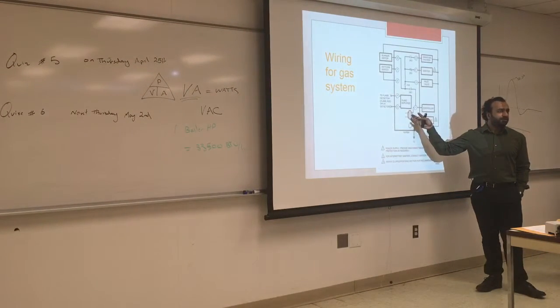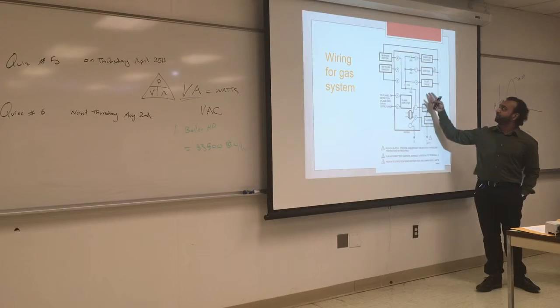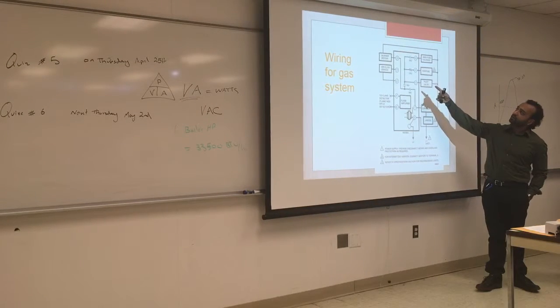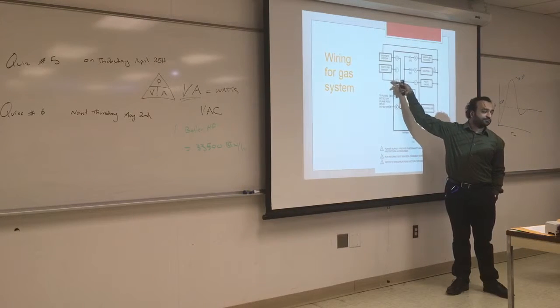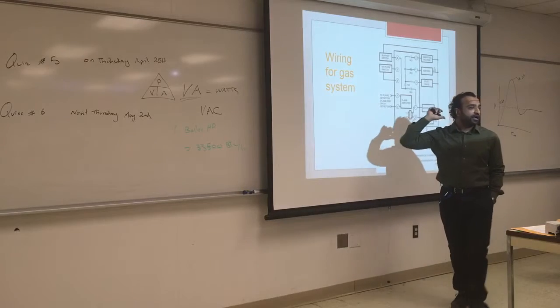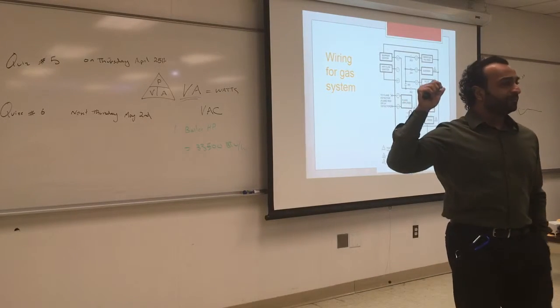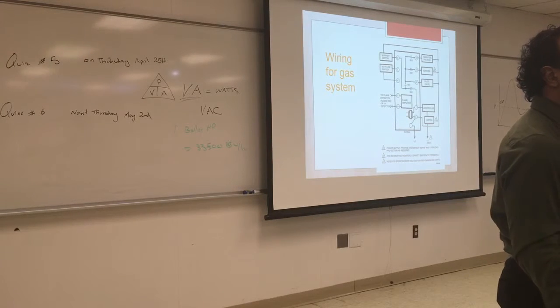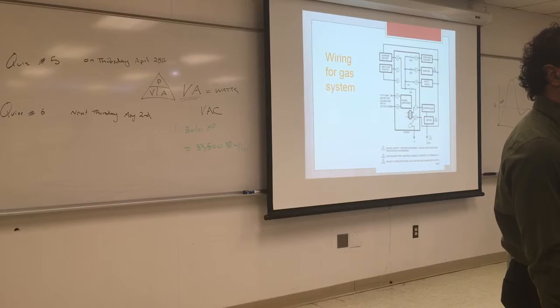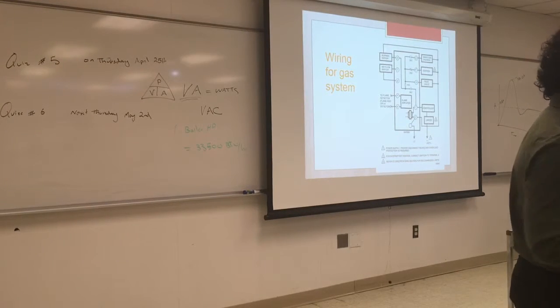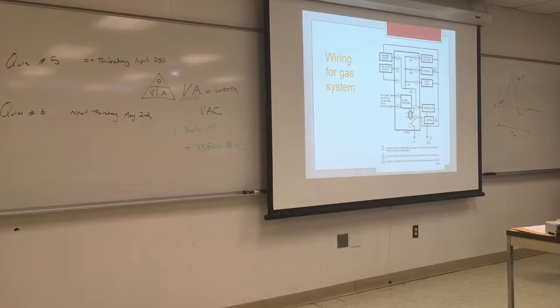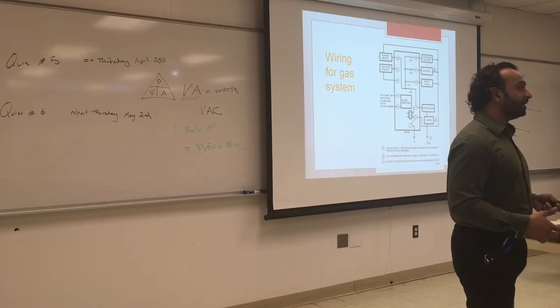It's very similar to the primary control. What is the difference here? You have a pilot, right? And you have a burner motor and airflow switch. This is the new stuff that we did not have before. And the airflow is very important for gas. Why is that? We did the lab yesterday and we looked at the gas and we said there are two airflow switches. Why do we make sure that there is airflow in the chamber for pumping gas? Because gas is compressible. And you don't want to compress a lot of gas in the chamber and have it leak out. If you don't have airflow in the chamber and you're pumping gas, the gas is going to come back. It's going to be pressurized, and once it ignites, it will look for the nearest opening and you see flame coming back, and that's when you have backfire.